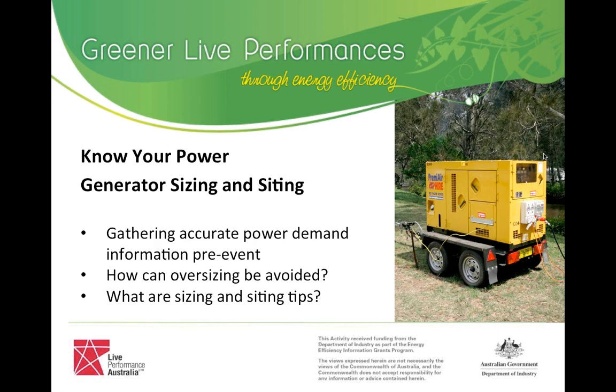So for an efficient event, you want to have smaller power demand where possible. But if you've got a hundred food stalls all needing bain-maries, that's a given. Where you then sit with your efficiency is to ensure you're using the right size generator and that it's being used at the optimal load — around 70 to 80 percent — as much as possible.